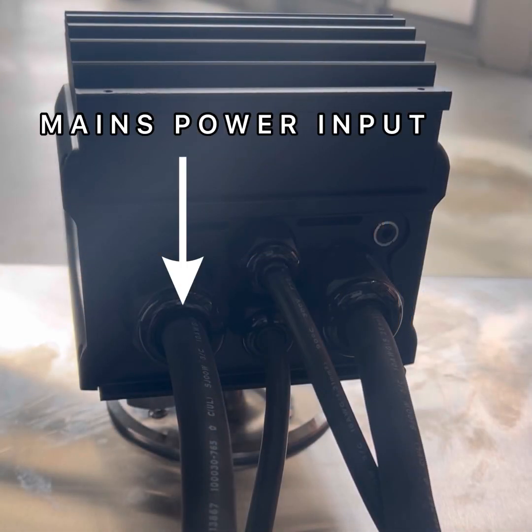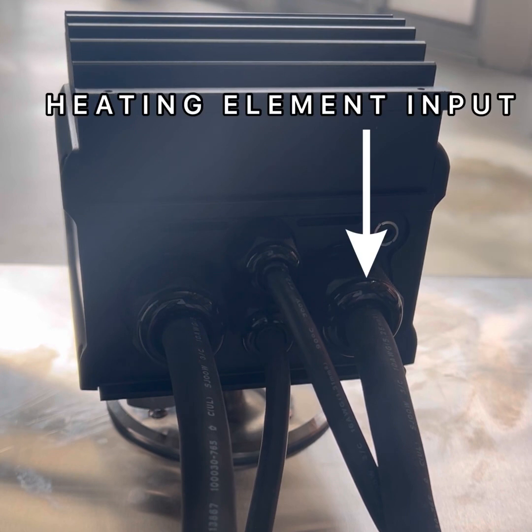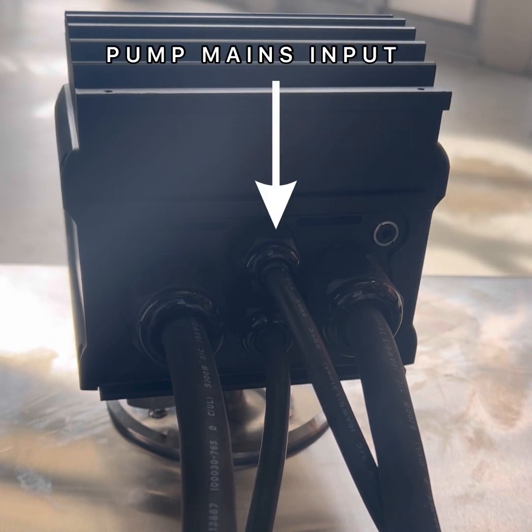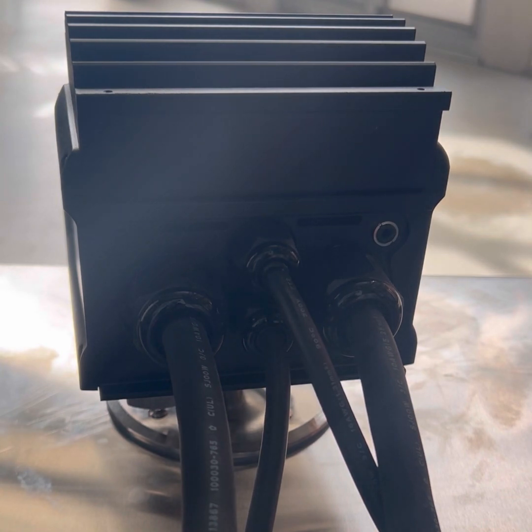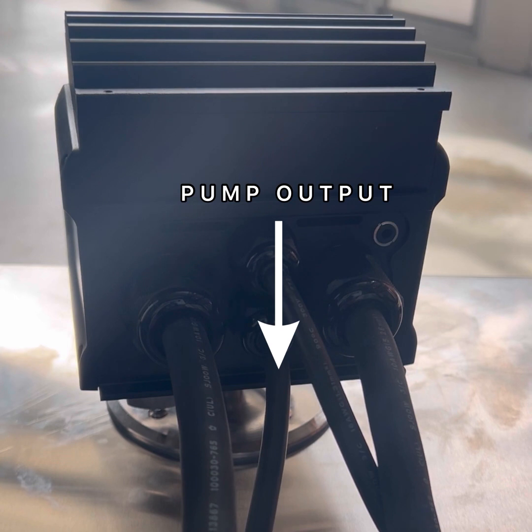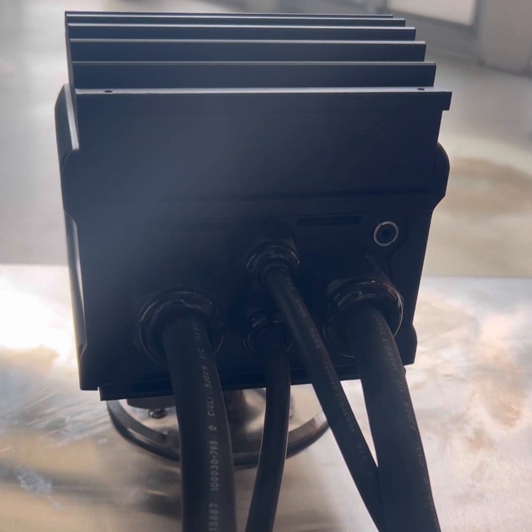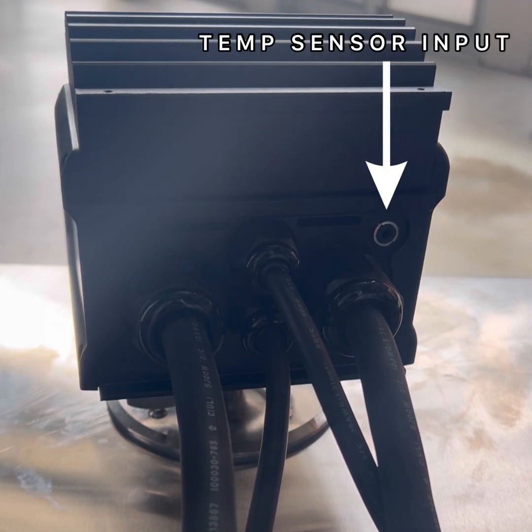On the back end of your NanoBoss, you will have a mains power input cord which plugs into your appropriate mains power outlet. A heating element input cord which your appropriate heating element plugs into. A pump mains input cord which plugs into a 10 amp wall socket to power the pump. A pump output cord which your 10 amp pump plugs into. And a temperature sensor input which your temperature probe sensor plugs into.